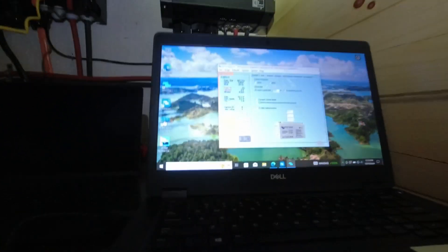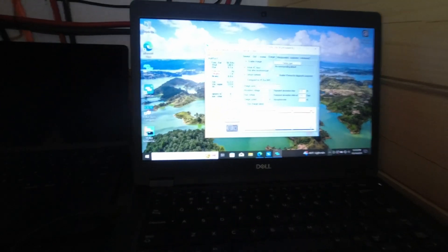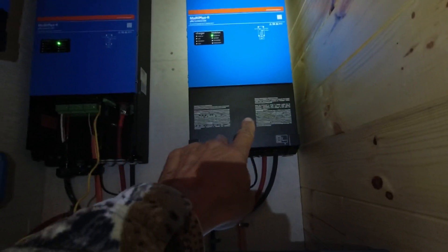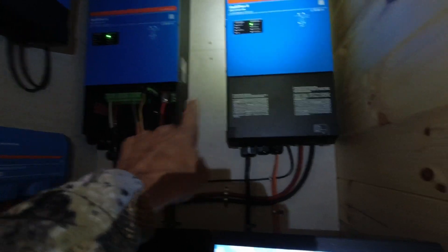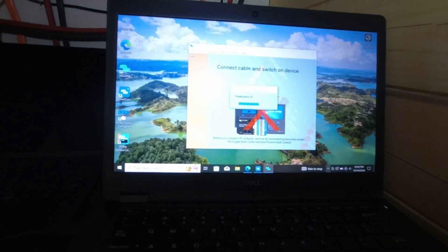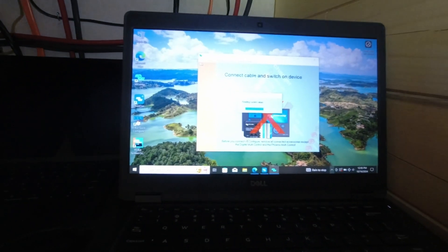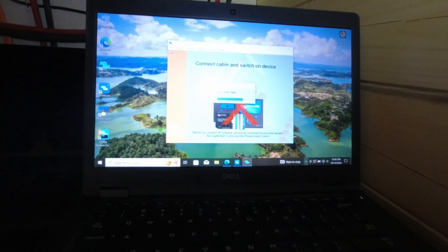I adjusted all the settings for the EG4 batteries with the proper voltages and I'm sending it to all devices right now. This is a master inverter and this is a slave, and there is a ground relay in it. I can only have one ground relay active, so I've got to go into this inverter and turn the ground relay off. I'm downloading all the settings from the slave inverter to verify they were saved properly. I'll show you where that ground relay option is — I think it's under General and it just needs to be unchecked.